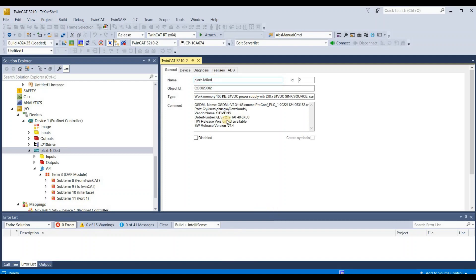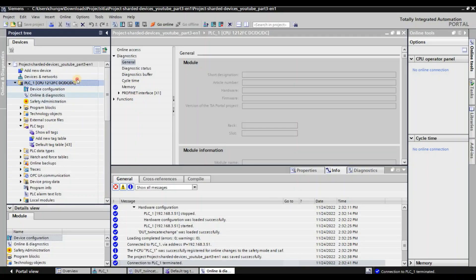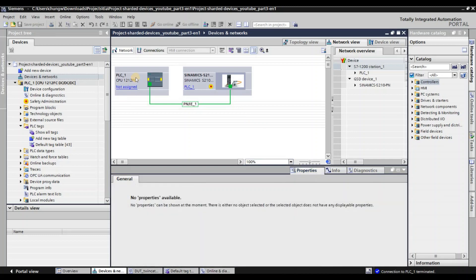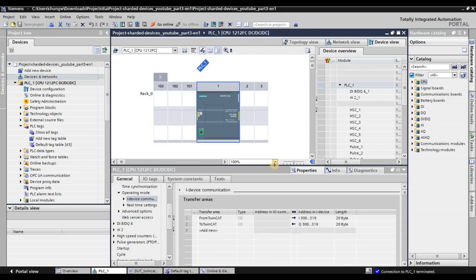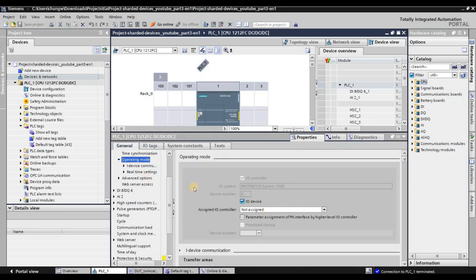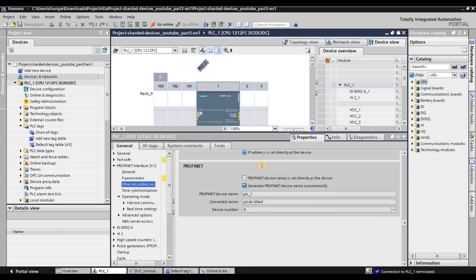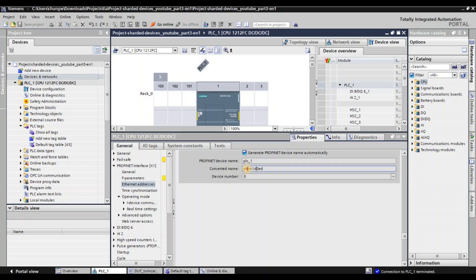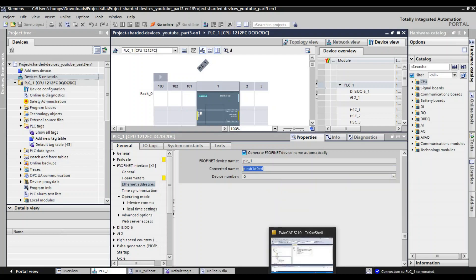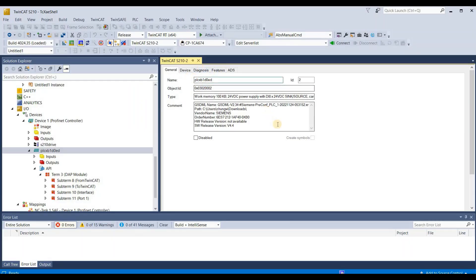In here, configure the IP address — I'll choose .51. We also need to configure the device name to match the S7 1200. As you see in the Siemens TIA project, the device name for the S7 1200 is 'plc_1'. In TwinCAT it shows as 'plcxb1d0ed' because there are conversion rules for underscores and special characters. Just make sure that the converted device name is 100% matching in your TwinCAT project.